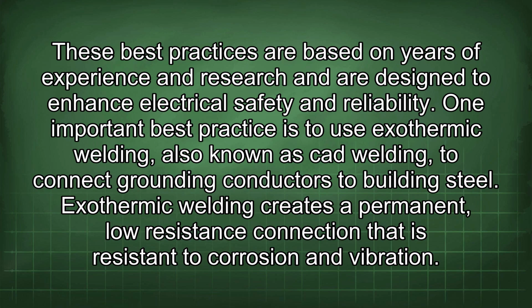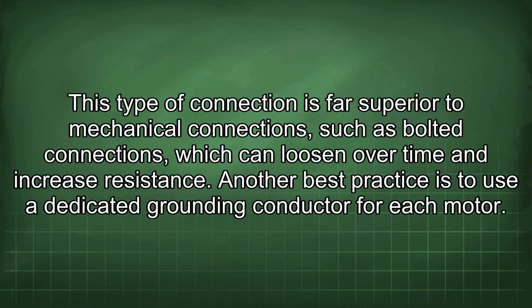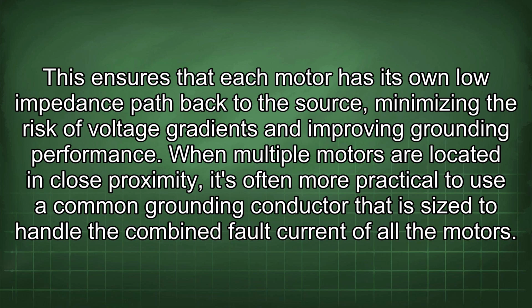One important best practice is to use exothermic welding, also known as CAD welding, to connect grounding conductors to building steel. Exothermic welding creates a permanent, low-resistance connection that is resistant to corrosion and vibration. This type of connection is far superior to mechanical connections, such as bolted connections, which can loosen over time and increase resistance. Another best practice is to use a dedicated grounding conductor for each motor. This ensures that each motor has its own low impedance path back to the source, minimizing the risk of voltage gradients and improving grounding performance.